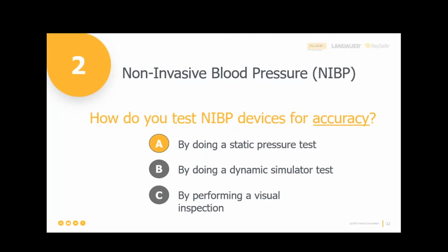Invariably, there may be a difference, but it's insignificant. Invariably. Okay. And if there is a significant difference, then fine. Then we'll remove that monitor from clinical use, replace it with another one temporarily, and we'll do deeper dive troubleshooting, which is going to be back to the static pressure levels and make sure it's all working well.